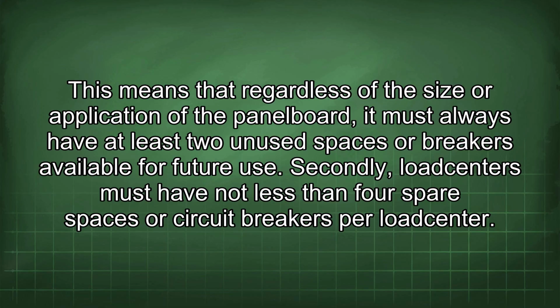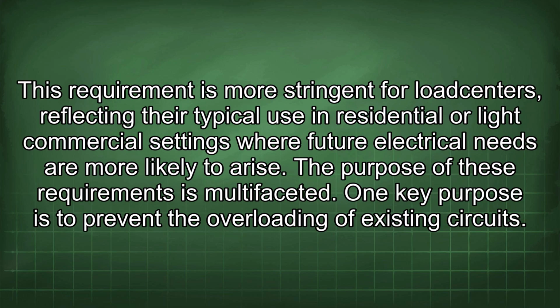Secondly, load centers must have not less than 4 spare spaces or circuit breakers per load center. This requirement is more stringent for load centers, reflecting their typical use in residential or light commercial settings where future electrical needs are more likely to arise.